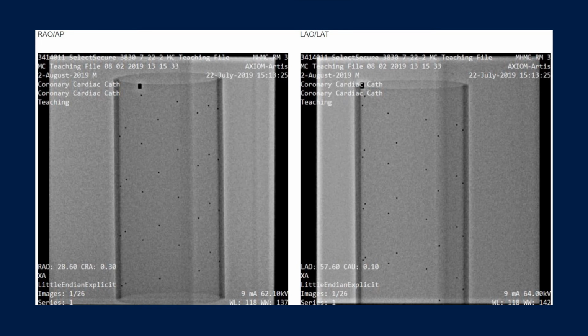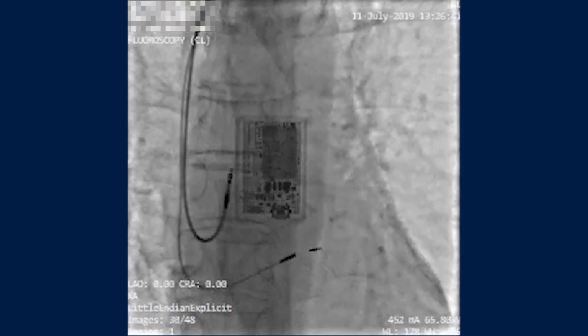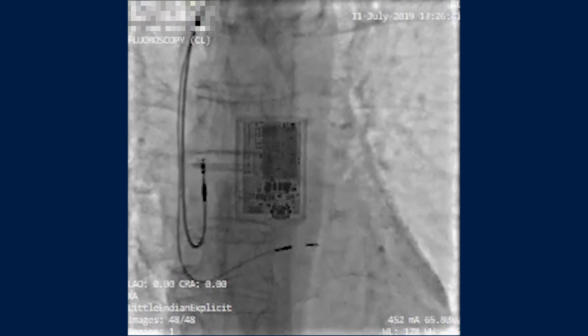Acquire a few seconds of BiPlane Cine on the phantom to include at least 13 BBs in both planes in addition to the large marker at the top. Here are good examples of intracardiac biplane images. The leads are clearly visible and in the middle of the image, and foreshortening is avoided in both views.